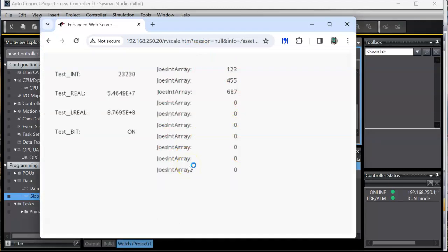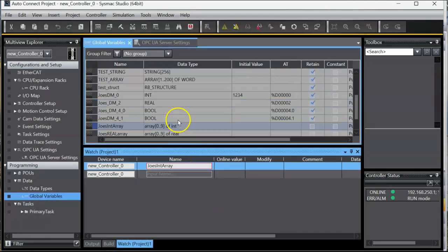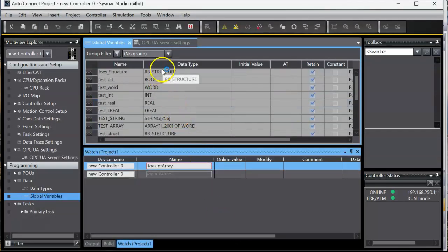The only type of tags that we could not get to work with the Omron is the structure type, which is a little bit deeper, where a structure has subtags under. That's a little bit deeper at this point, and currently the OPC UA driver does not support that in the RedLion Crimson 3.2 environment. Maybe in the future we'll add that to a different version of Crimson, but right now it doesn't. But all the other ones, I can talk to any of them. So the only trick here is the Omron.